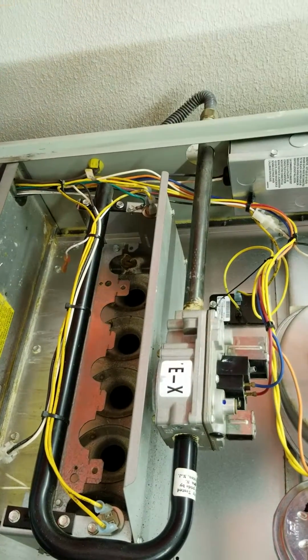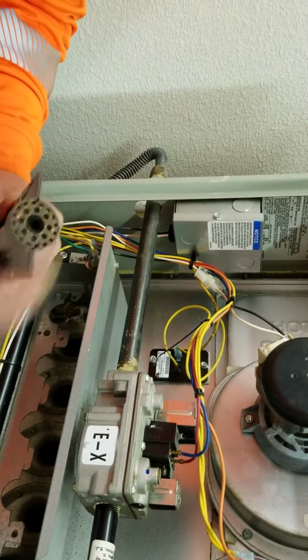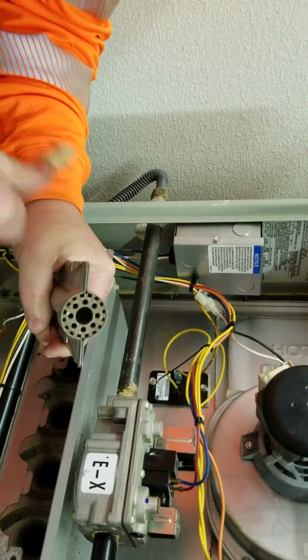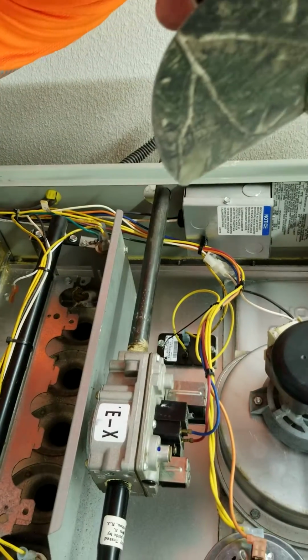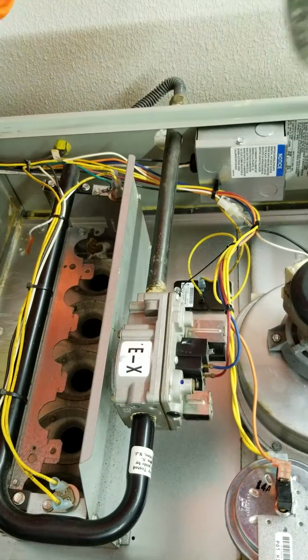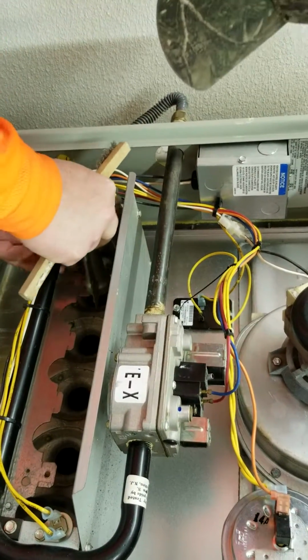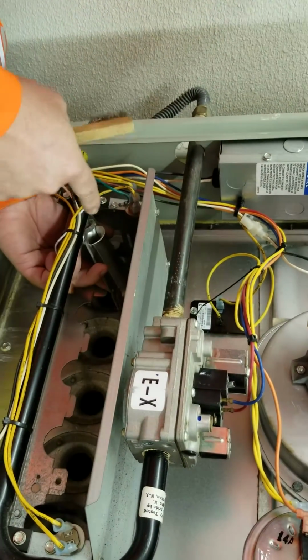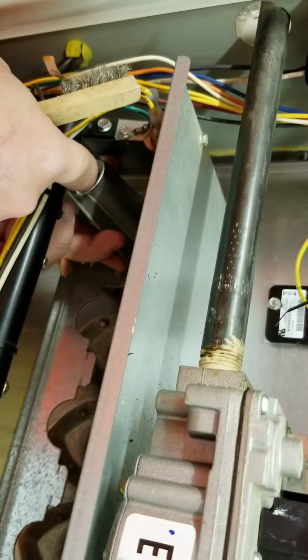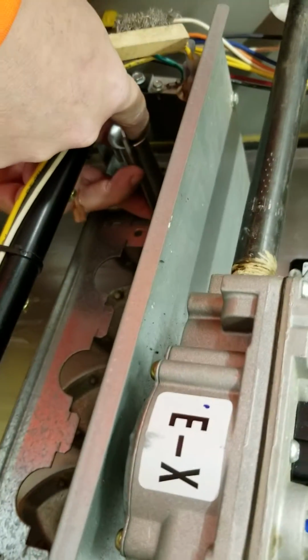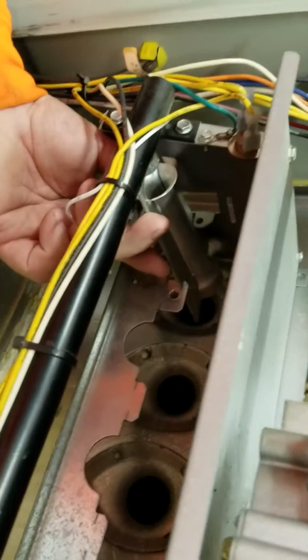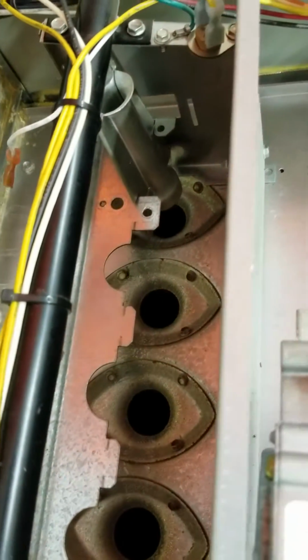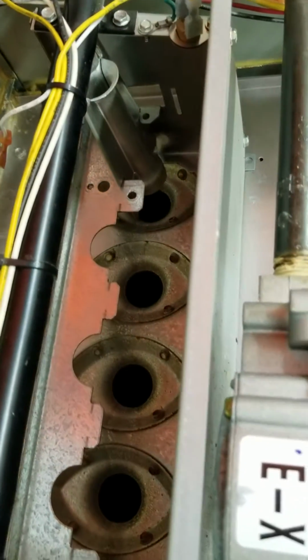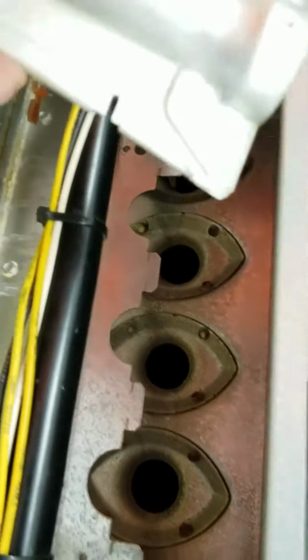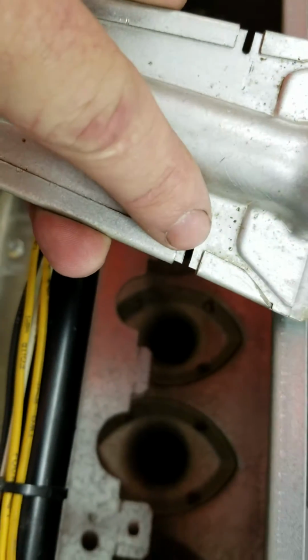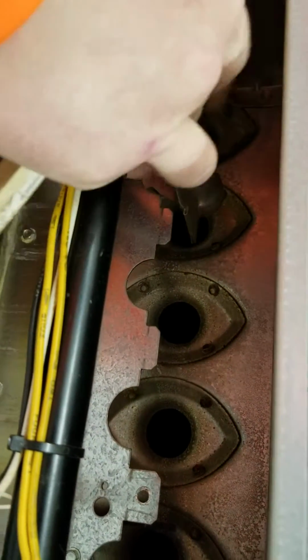One. There's one there, 2. Now what you can do is, as you clean them, you can go ahead and put them back in place if you want to. And make sure that the round guide on the side of the burner facing you goes over the burner spud. Then there will be, in this case, 2 slots on the side of the burner that slip onto the holders, onto the burner holder.